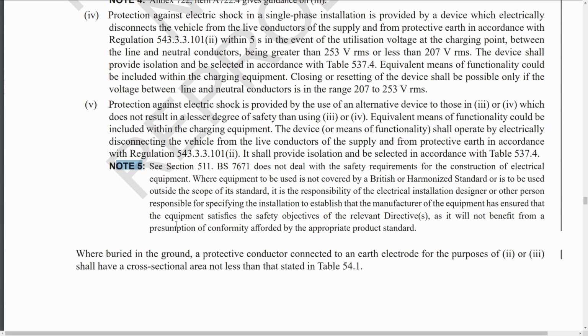So in other words, you still need to get some kind of evidence from the manufacturer to confirm that their device or mechanism or whatever they've made does provide the appropriate degree of safety when it's installed in these circumstances with a TNCS supply. But at least this does give the option there to install things which say either are new on the market or say don't even exist yet and will be available in the future. Say that, yeah, provided manufacturers saying that it covers whatever, then you can install it and it will comply with BS7671.